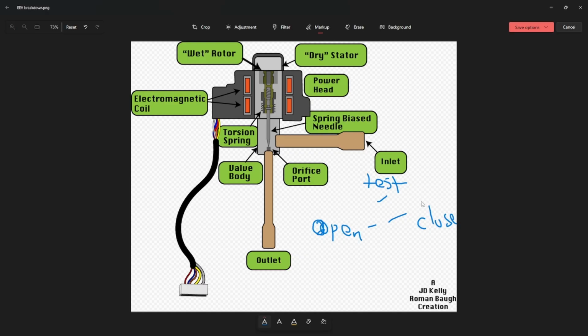When you do the open or close test is when you can check the DC voltage on the Molex. Again, the service facts tell you what the DC voltage is supposed to be. I do not have that information memorized like I do the resistance readings of a stepper motor.